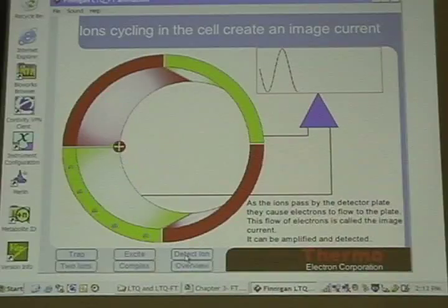So the number of ions we put into the trap has to be significantly higher. A typical setting for the ion trap might be 20 or 30,000 for full MS. A typical setting for the FT would be anywhere from 500,000 to 1,000,000 ions. It is less sensitive if time is a factor. If I give you the same amount of time to fill the trap, then the FT is less sensitive. If time doesn't matter, and I don't care how long it takes to fill the trap, then their sensitivity is equivalent.